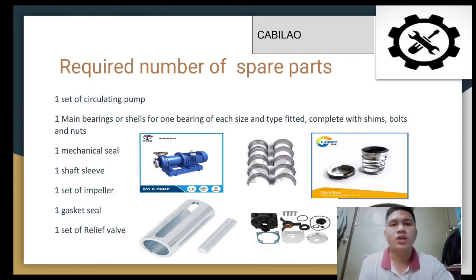Next is a shaft sleeve. A shaft sleeve is a hollow metal tube, and its basic function is to protect the shaft from packing wear at the stuffing box. Shaft sleeves also help to protect the running surface of the shaft seals, or the surface in contact, from damage or abrasive wear. Next is impeller. So we also need one set of impeller.